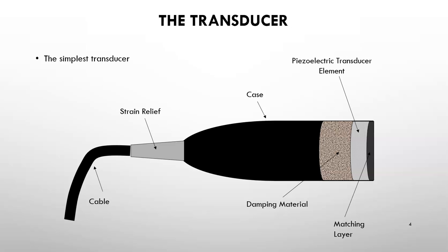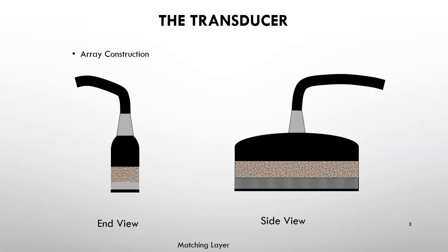Now, most of the transducers we use today are phased array transducers. And when I say array, what I mean is that there are many elements within the transducer that are lined up one after the other in a single line or array. These array transducers, the simplest ones, have a crystal across the width, and then many crystals along the length of them. Or I guess you could say this would be the width or the length, and then this would be the width of it, whichever.